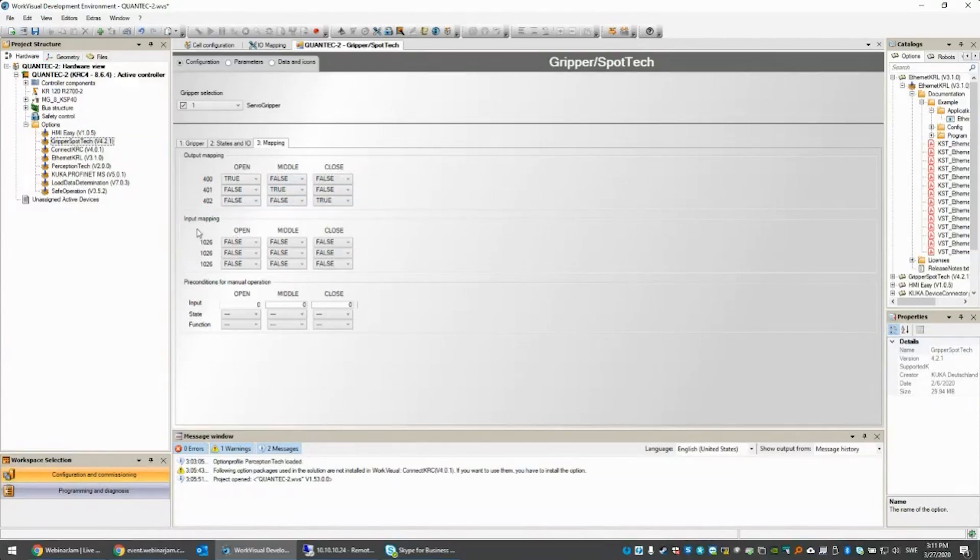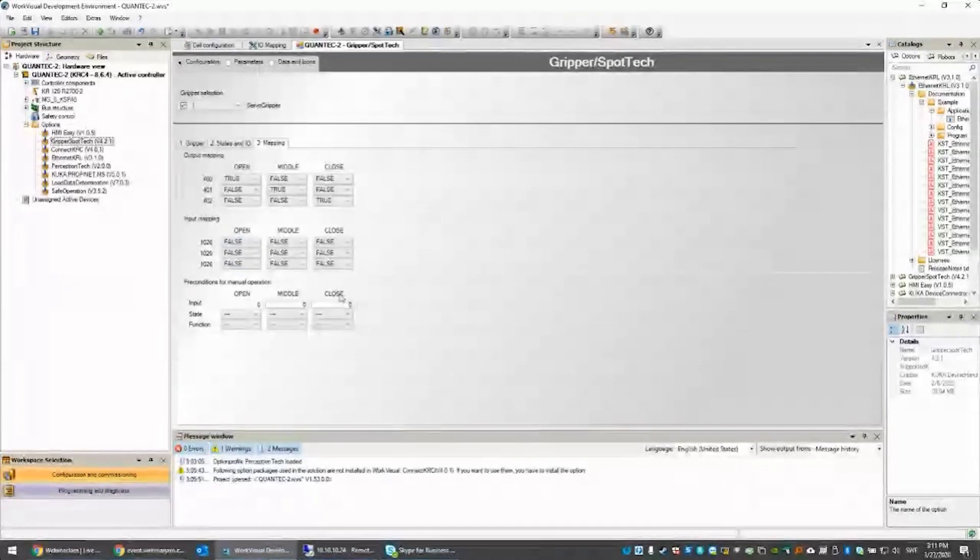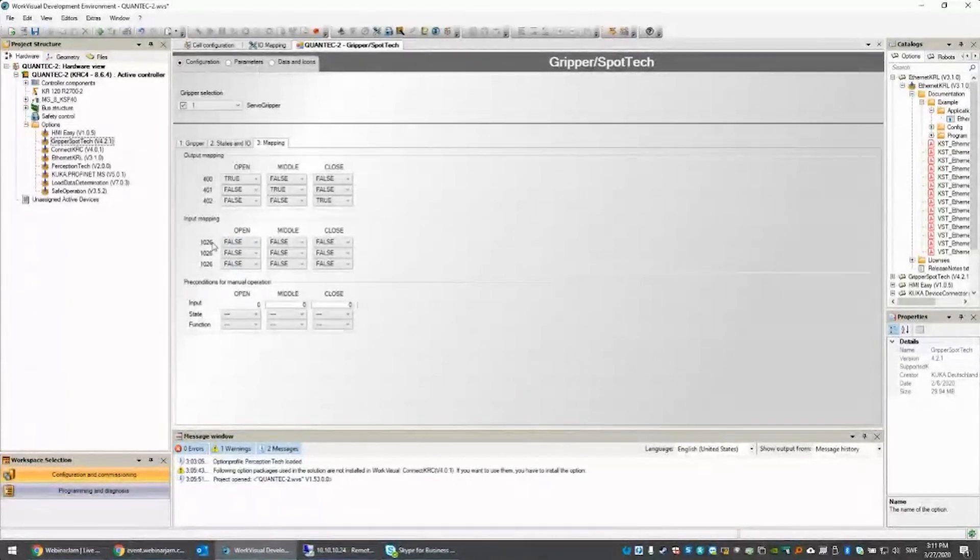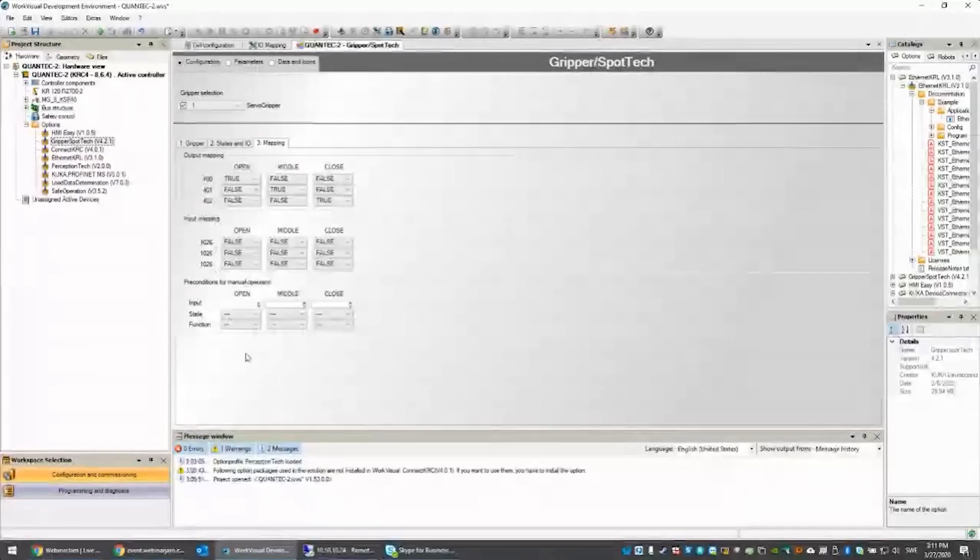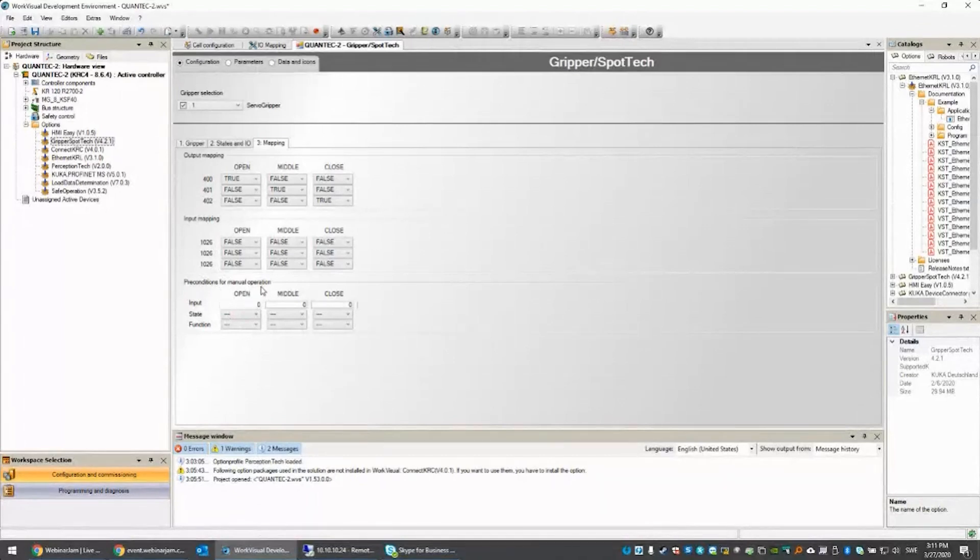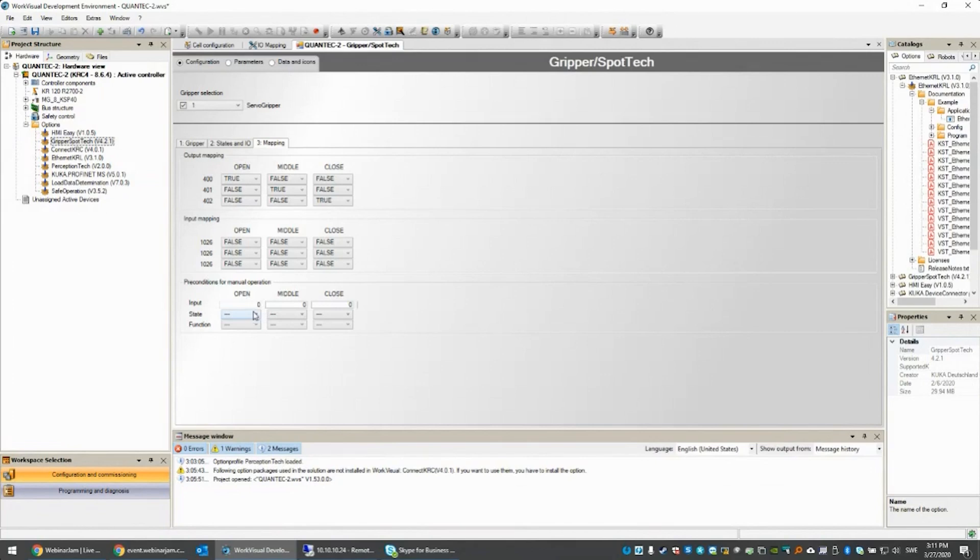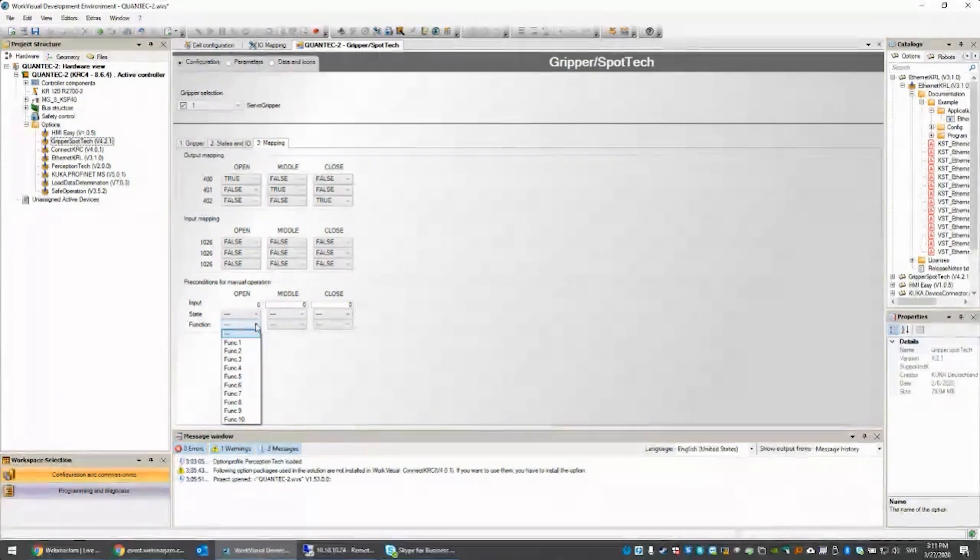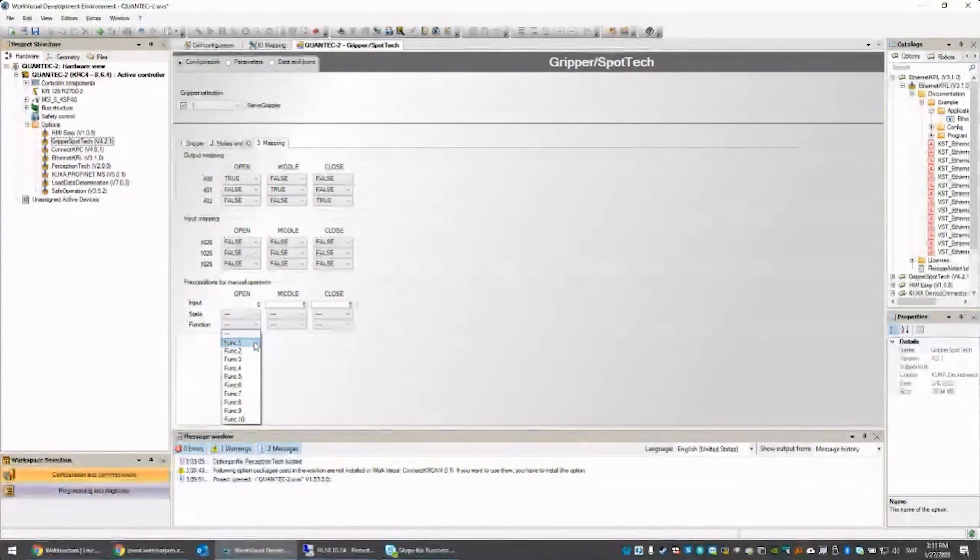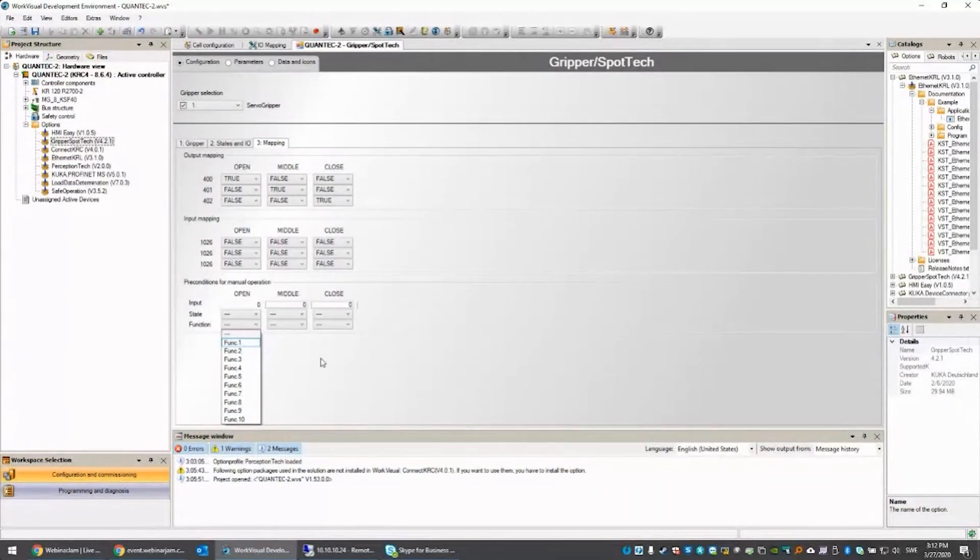Then we have the input mapping. In this case, I'm not even using them, so they are false. That signal is always false. You also have the possibility to have preconditions for manual operation. If I select this input, this input has to be true in order for me to manually open the gripper. That can also be linked to functions, which are basically created in KRL.